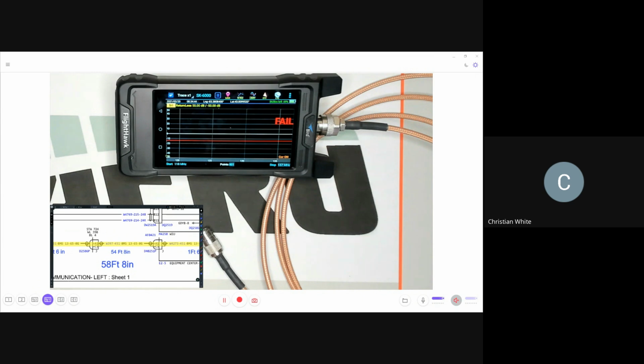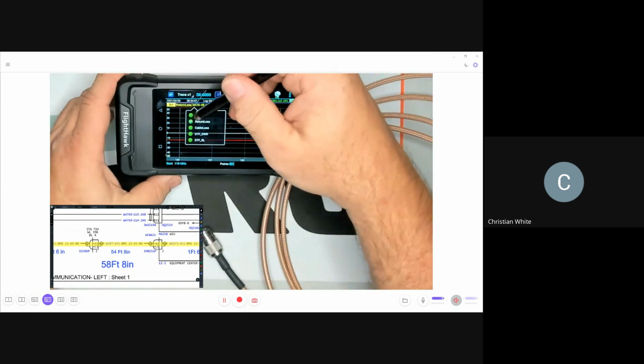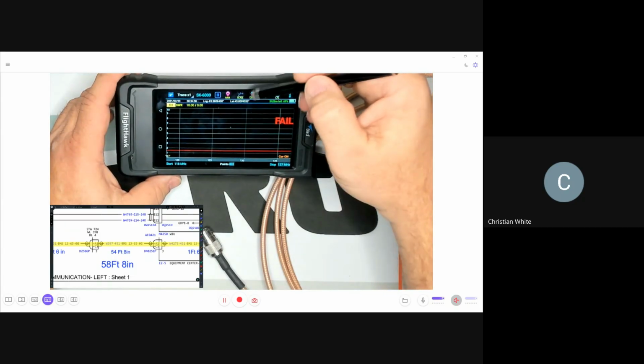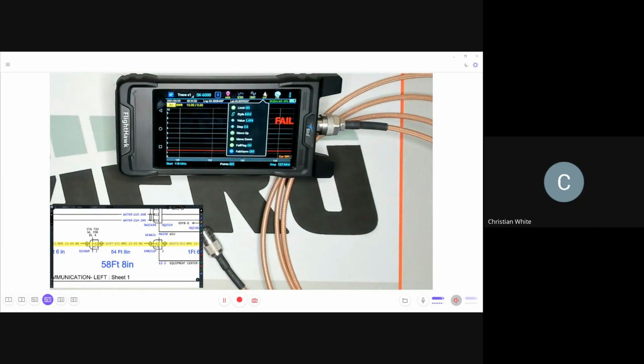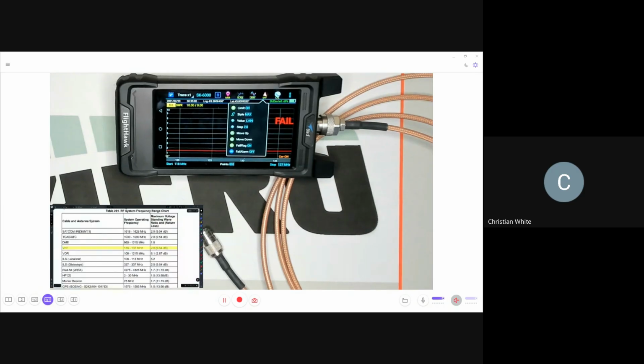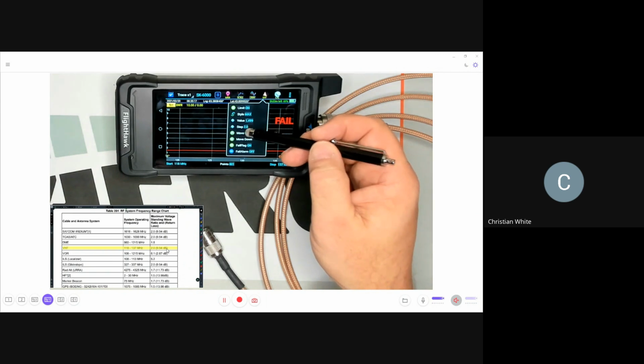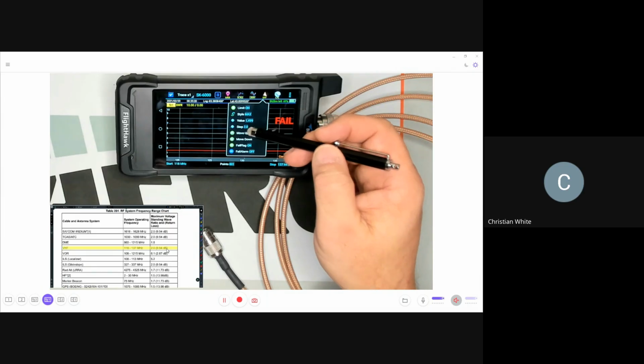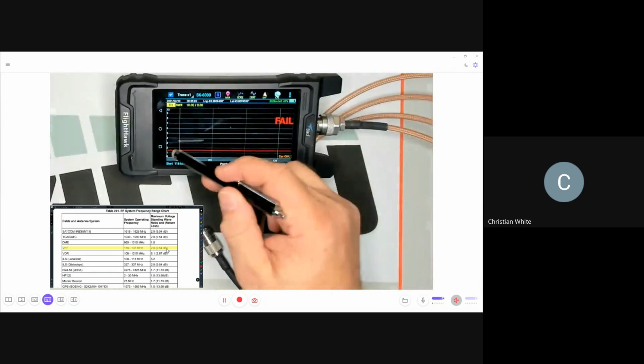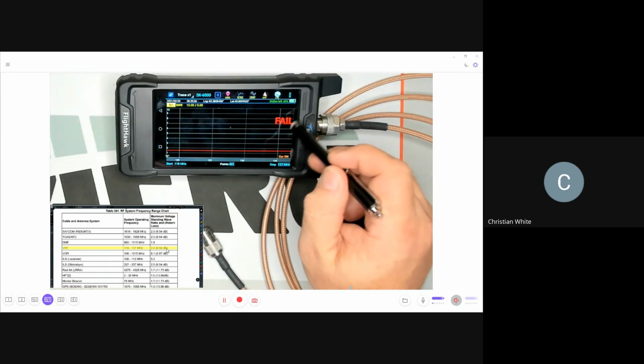Now all we do is measure this in SWR - that's what we set up for. If we go back to our chart in the AMM and look at that 2.0, we're going to do SWR. We just changed this to SWR, and our limit is going to be 2.0. In this case, it's already at 2.0, so we don't have to change that, but this is where you would change it. So now we have our limit, we turned on our little red fail line and our fail flag.